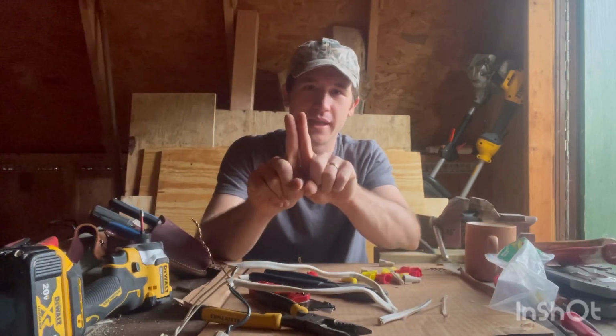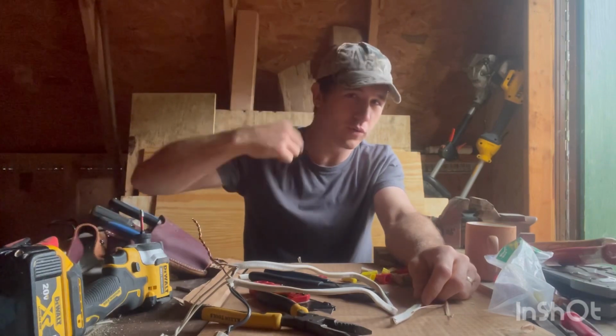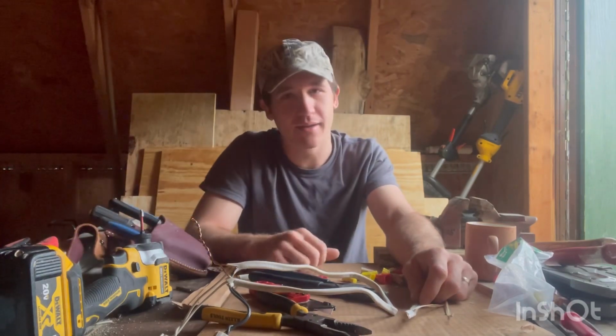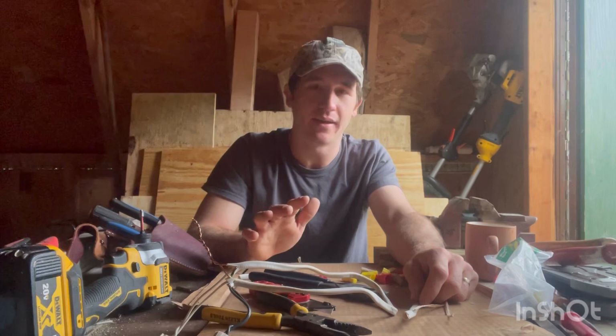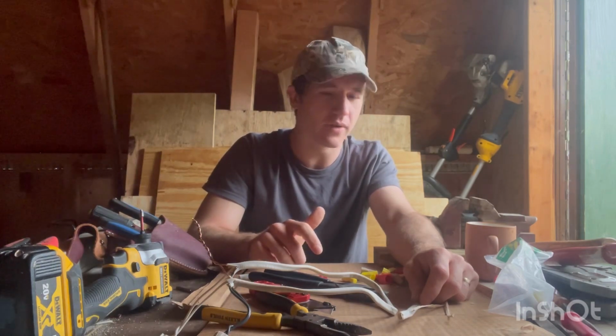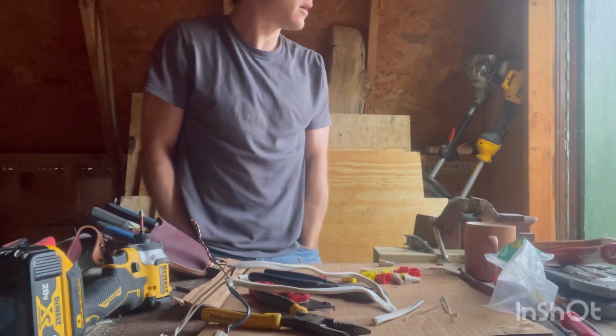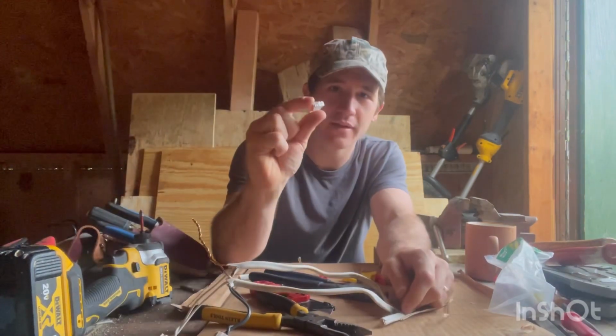So now that you've seen this video, you've got no excuse to be taking 2 wires, putting them together like that, taking a wire nut and twisting it over it, and then putting a whole roll of tape all the way around it. That tape is not doing anything. That tape is not helping you in the slightest. Furthermore, you've got no excuse to be using one of these.